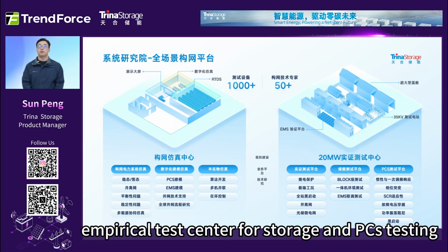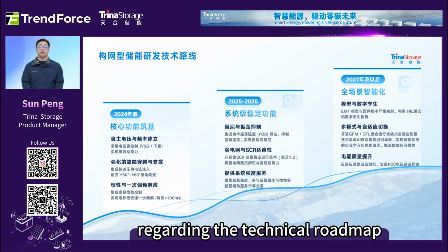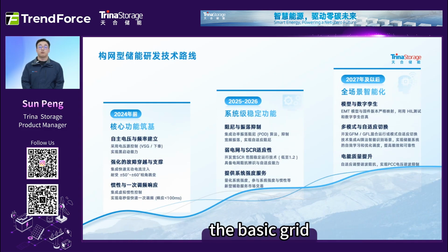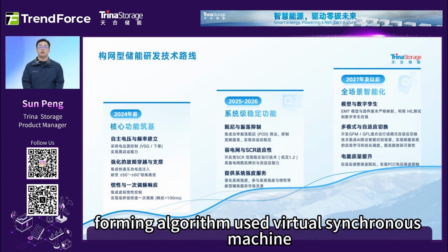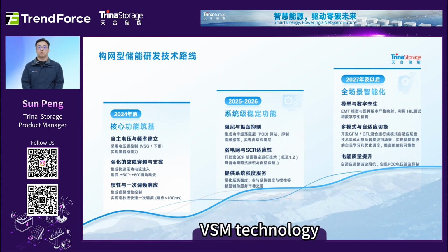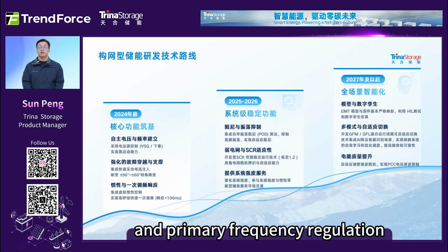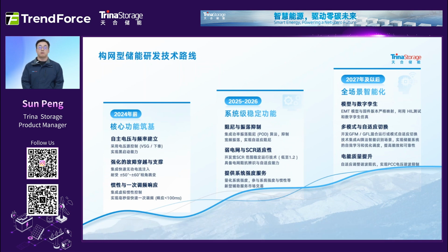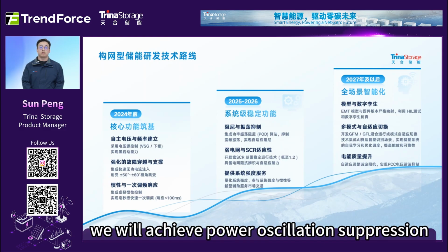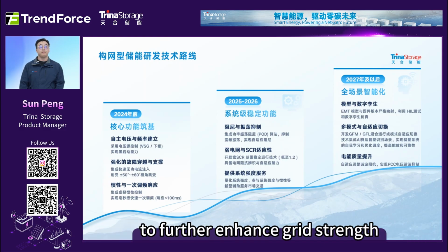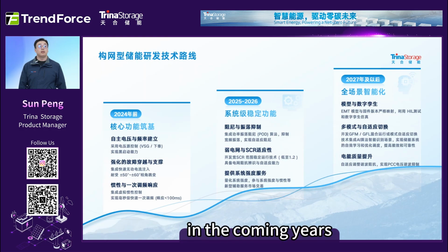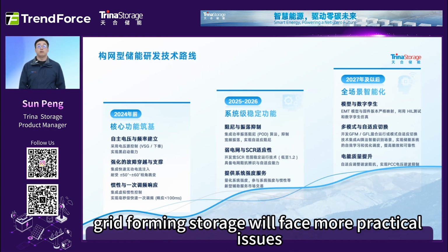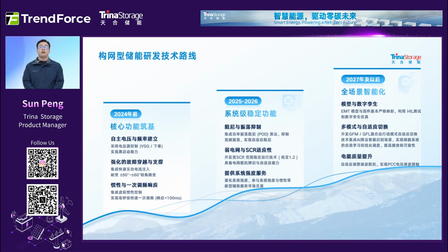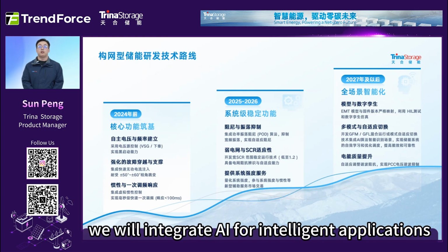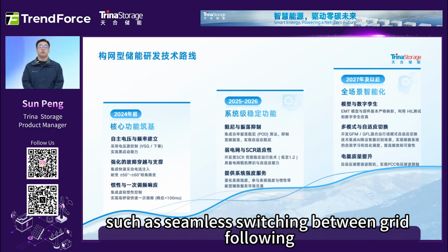Regarding the technical roadmap, in previous years, the basic grid-forming algorithm used virtual synchronous machine (VSM) technology to achieve inertia response and primary frequency regulation. Within the next 2 years, we will achieve power oscillation suppression to further enhance grid strength. In the coming years, grid-forming storage will face more practical issues. With the rapid development of AI, we will integrate AI for intelligent applications, such as seamless switching between grid following and grid forming modes.